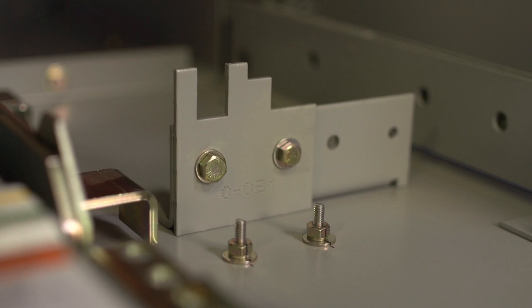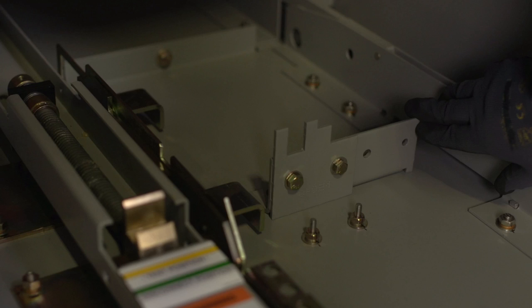Next, we have the interference blocking plate or coding interlock, which prevents the incorrect size circuit breaker from being inserted into the cell. And to the right of that is the interference plate position, which is used as an option if special interlocking is needed for an electrically operated ground test device.